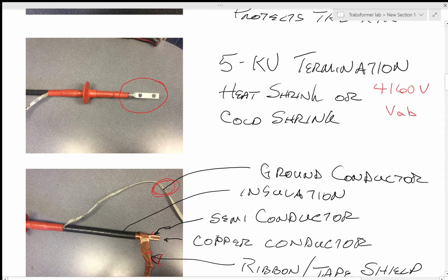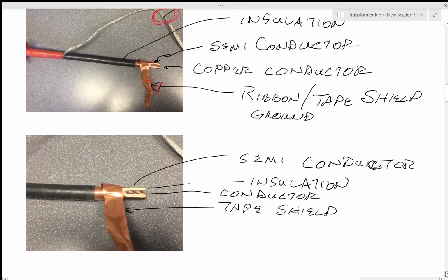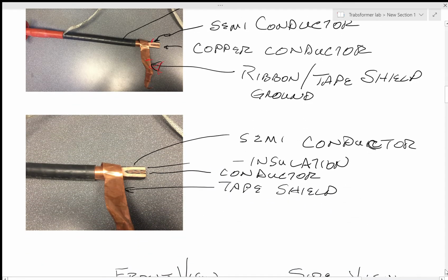Let me get a little bit better picture of this. Yeah, here we go. So you got the insulation right here. That's that yellowish stuff. You got the semiconductor, which is black. And like I say, it keeps the eddy currents contained. You've got, in this case, a copper conductor. It's not an aluminum conductor like the other one. And then you've got the tape shield. It's just like a band of tape around there, and it keeps everything together.